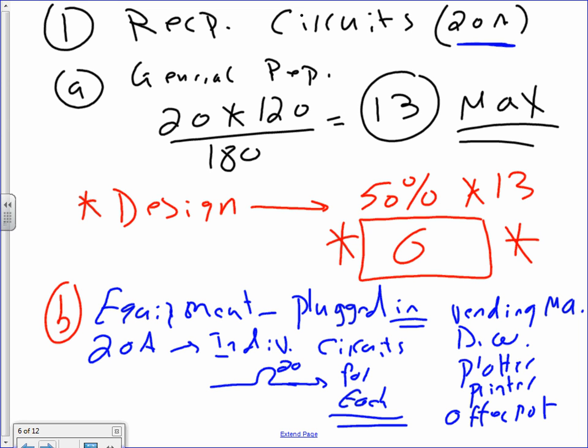So general receptacles. If you do general receptacles based on the code, you take a 20 amp circuit, right? Multiplied by 120, right? Everybody knows where the 20 came from. That's the amps. Where did the 120 come from? We wire the receptacles in the US at 120, the convenient receptacle. Divide by 180 volt-amps. Does that ring a bell, the 180 volt-amps? That's the one that we use for all the calculation for receptacles. It gets you 13 receptacles maximum. Maximum 13, no matter what you do. The reason we use 20 amps here is because general purpose receptacles are not considered continuous. So here's your max. No matter what you do by code, you can't put more than 13 receptacles on a 20 amp circuit, right? That's the max.